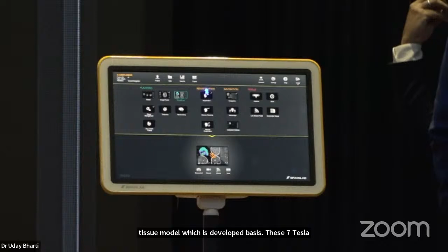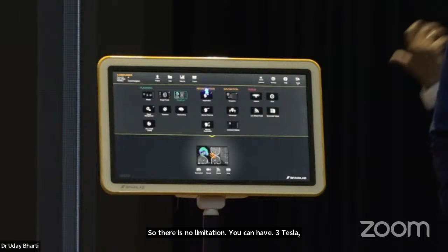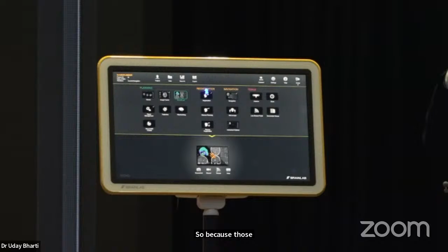So there is no limitation. You can have 3 Tesla, 7 Tesla MRI. The only thing is it will add up to the distortions, which you will have to compensate, because it's the common concept. If the sensitivity increases, then it will pick up small distortions also. So that is why you need a distortion correction, and especially when we are doing DTI sequences, because those DTI are done at a 2 mm or 3 mm slice thickness. This is their basic property.